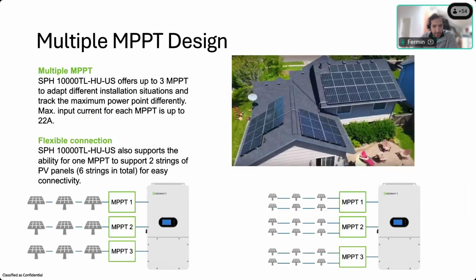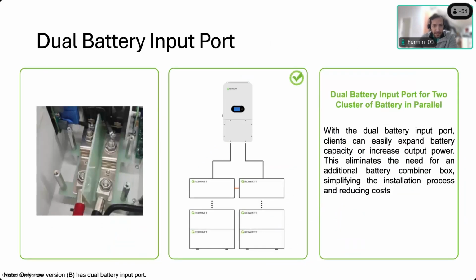As I previously mentioned, it has the 3 MPPT ports. Each MPPT port allows you to connect up to 2 strings in parallel for 3 different array orientations. It comes with a dual battery input port. Make sure the version that you order is the B version. These battery ports are rated for 200 amps. So this eliminates the need for a combiner box to parallel multiple battery strings.